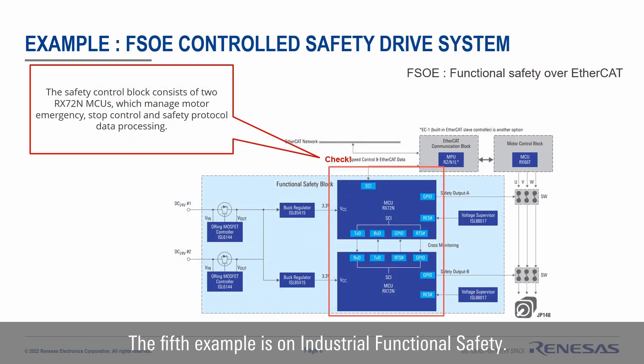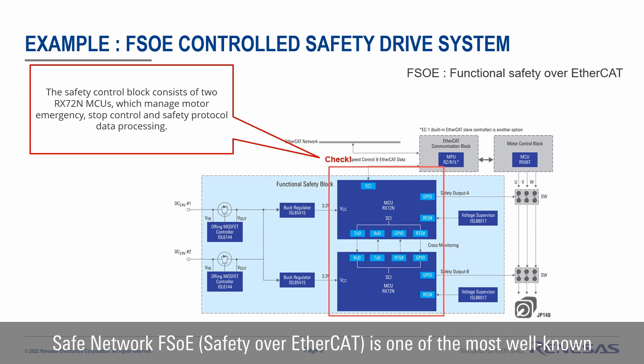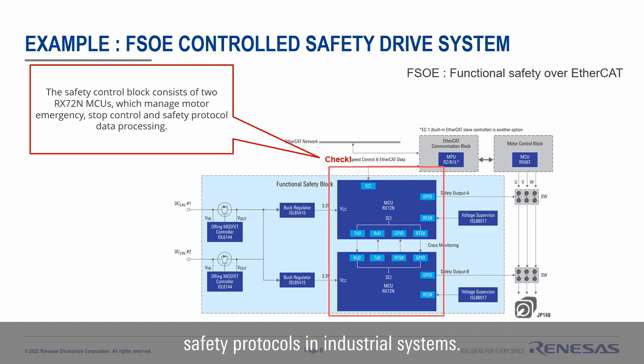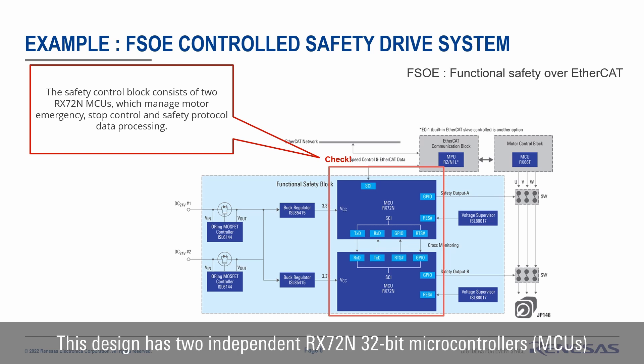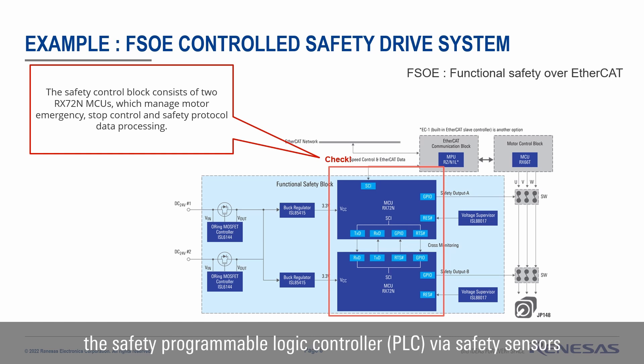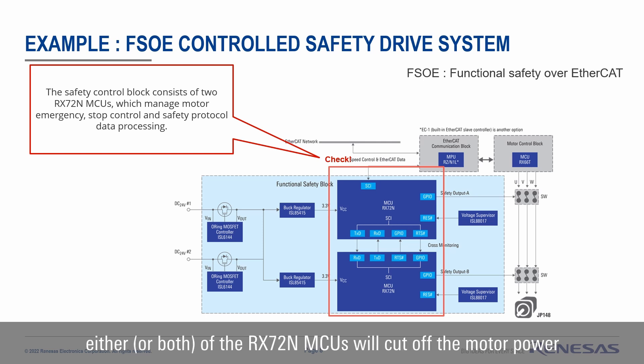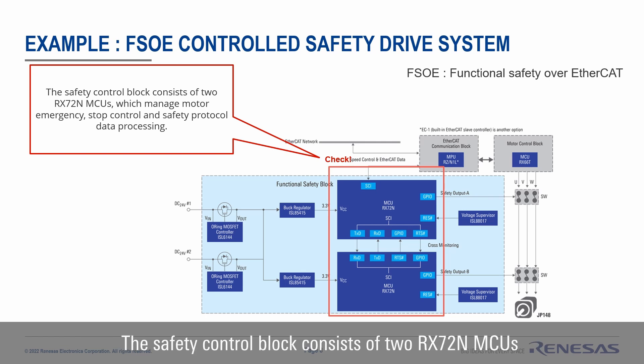The next example is for industrial functional safety. The system features secure industrial network control and secure motor drive. Safe network FSOE is one of the most well-known safety protocols for industrial systems. This design has two independent RX72N 32-bit microcontrollers that maintain control and safety cut-off power to the motor in the event of a system failure. Safety data such as emergency stop comes from the Safety Programmable Logic Controller via safety sensors or EtherCAT communication blocks. This safety data is checked separately by both RX72N 32-bit MCUs, and if either indicates an emergency, either or both will cut off the motor power to prevent a dangerous situation.